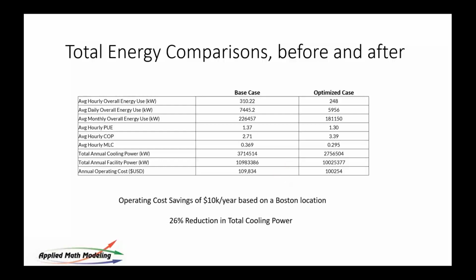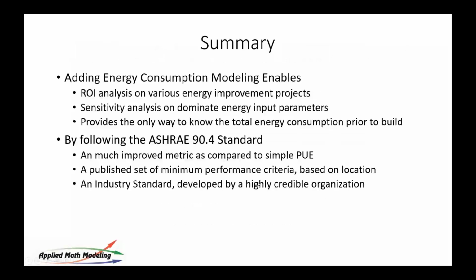Mm-hmm. But we've seen a lot more from the mechanical side, and we didn't get a chance to, well, in this case, it was an air-cooled chiller, so it was a box. There's not much you can do. But when these things are broken out, like we did a project recently where we had a cooling tower, we had a separate chiller, we had a plate and frame heat exchanger, we found the opportunity for energy savings there was higher because you could get sort of inside the box and make changes to specific components that allowed for optimization. And we gained a lot just from things like adding VFDs and so forth.